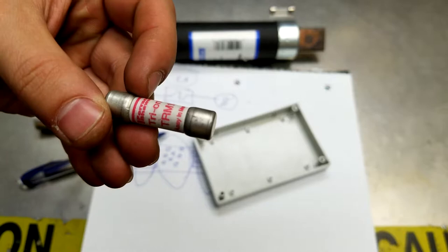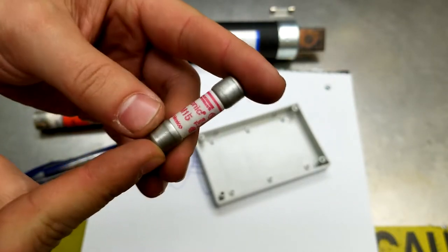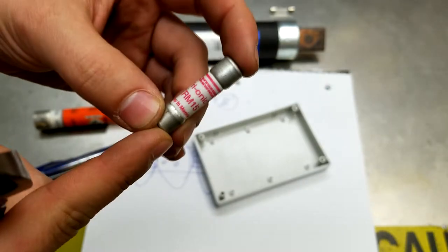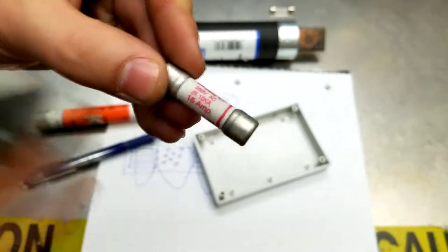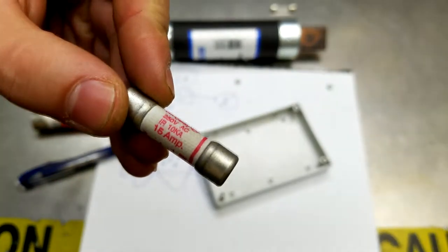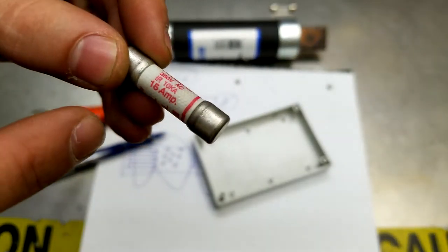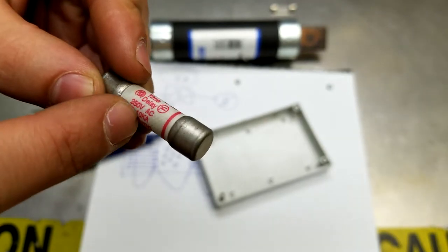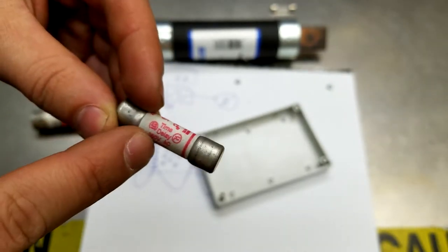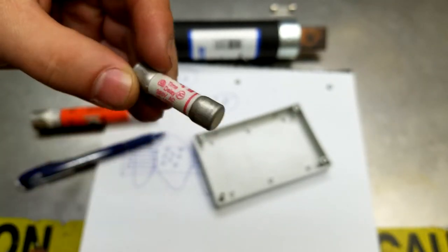So this particular fuse is a 15 amp fuse. Tri-onic, Ferraz Shawmut, made in, no, assembled in Mexico. But it does sound German. Capability to stop 10 kiloamps. It's a 15 amp fuse, 250 volts rated, time delay. Okay, very important.